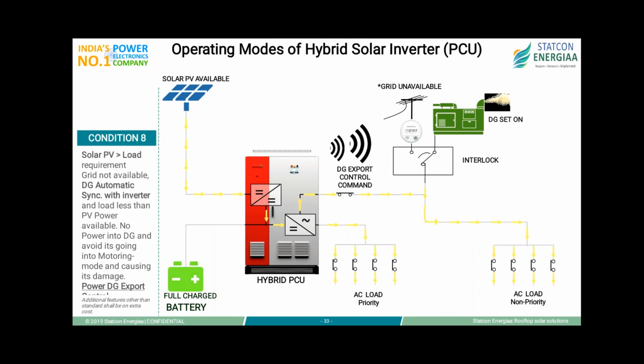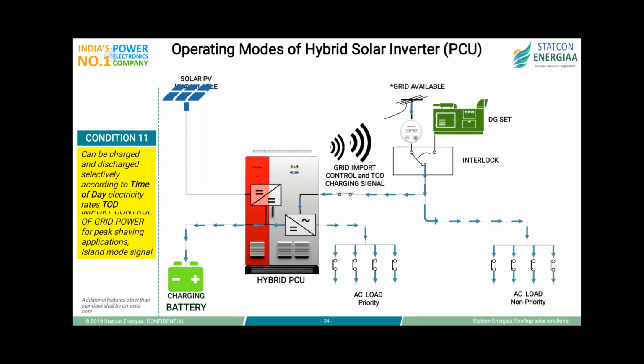Here we are talking about DG export control command. So there are applications like peak load shaving in all the medium level plants and growing factories, where today they have a certain size of load and then their load increases, or for some instance they have a peak load. So they end up paying penalty on the entire bill, which should not be the case if a hybrid inverter is installed. The battery or the solar can take that burden. Battery can be momentarily discharged to load so that your load doesn't go beyond the sanctioned load.